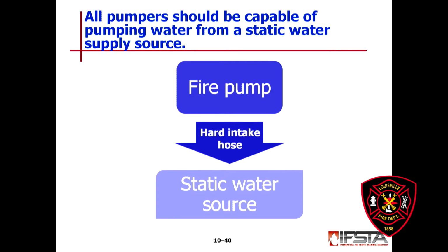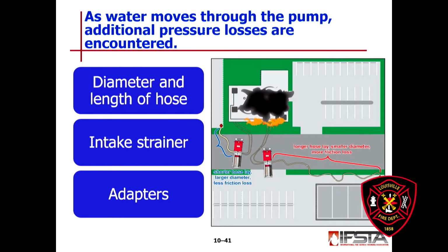And again, what we're doing is pulling air out of the fire pump itself, dropping the pressure below atmospheric pressure so that water is now forced from that static water supply source into the fire pump. We do encounter some pressure losses when we do this: diameter of the hose, length of the hose, the intake strainer, as well as any adapters.